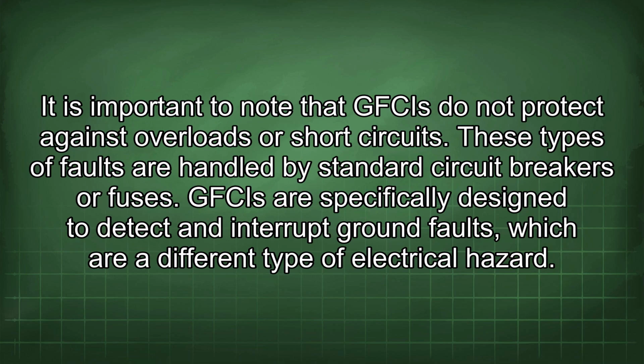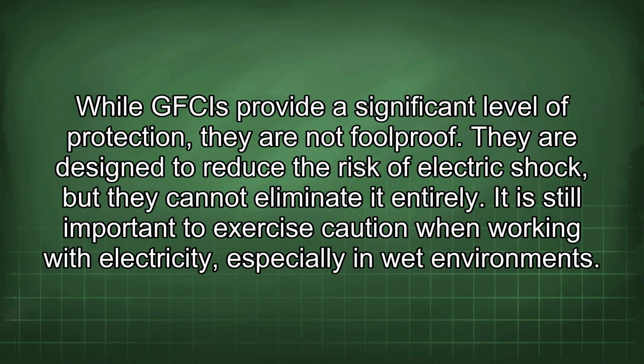It is important to note that GFCIs do not protect against overloads or short circuits. These types of faults are handled by standard circuit breakers or fuses. GFCIs are specifically designed to detect and interrupt ground faults, which are a different type of electrical hazard. While GFCIs provide a significant level of protection, they are not foolproof. They are designed to reduce the risk of electric shock, but they cannot eliminate it entirely.